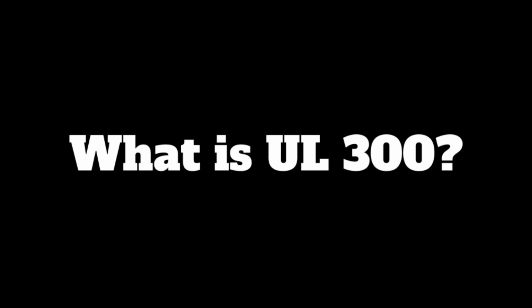What is UL 300? UL stands for Underwriters Laboratories. 300 is the test number that was used for this specific test. It was brought about due to changes within the cooking industry. Newer appliances burn more efficiently. They changed the oil that was being used from lard to more like peanut oil or vegetable oil because it burns at hotter temperatures. The old systems used to use powder, and they worked fine at that particular time, but now with the newer appliances burning more efficiently and hotter, the change had to be made from dry systems to wet systems. Those changes demanded more rigorous testing methods, and that was why UL 300 was established in 1994.